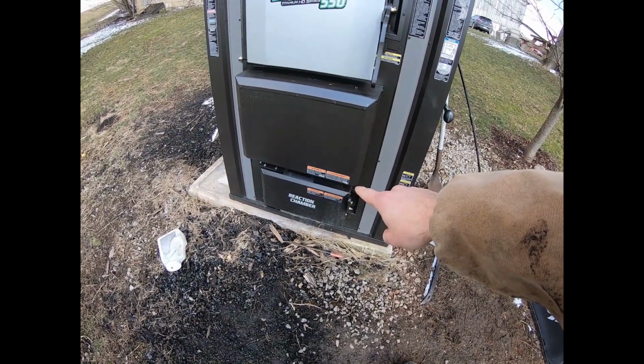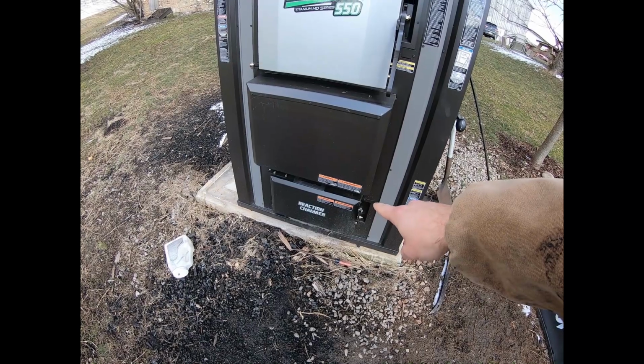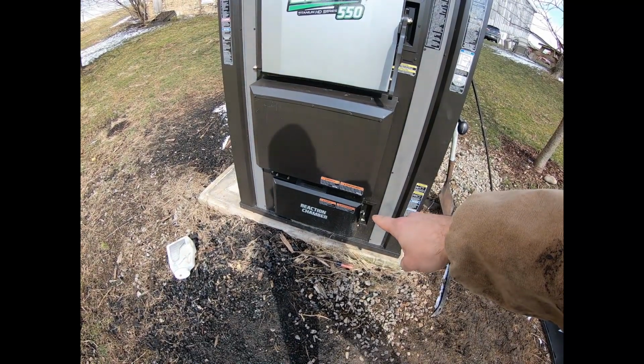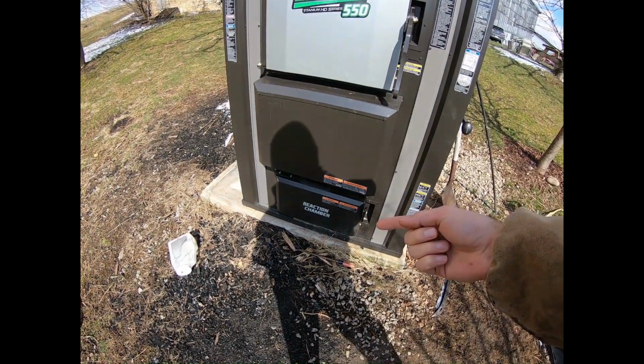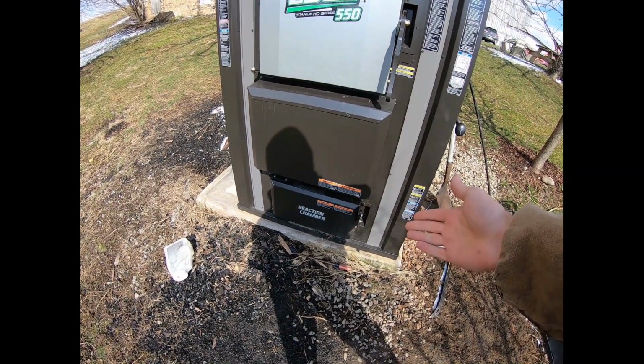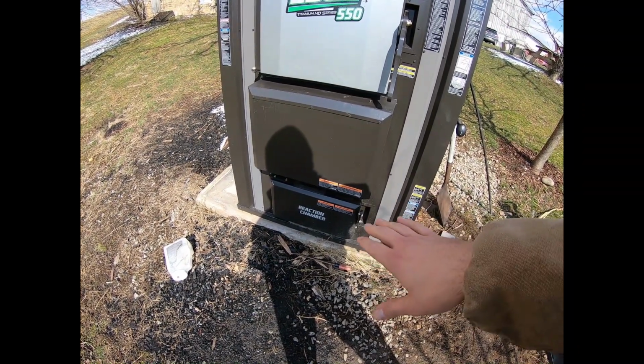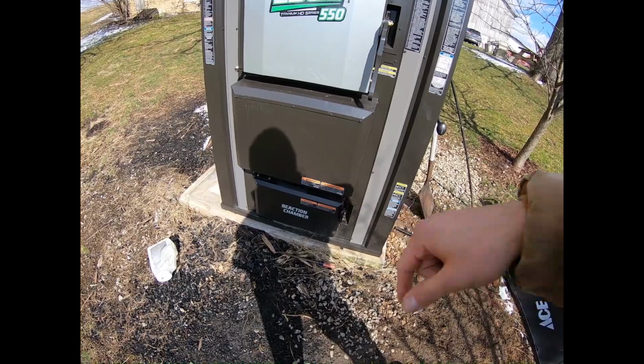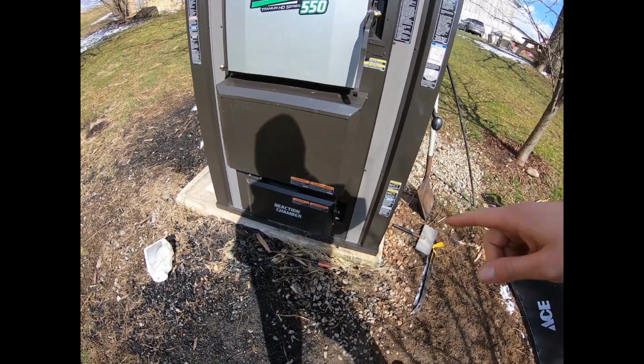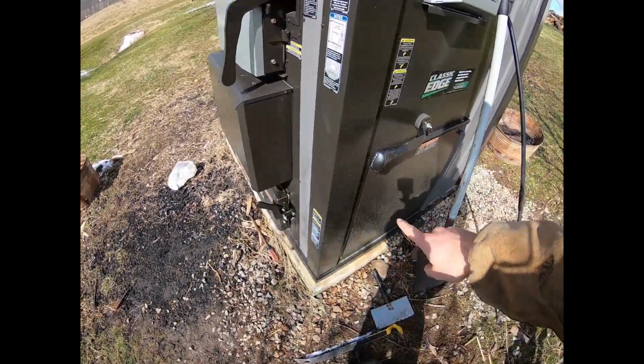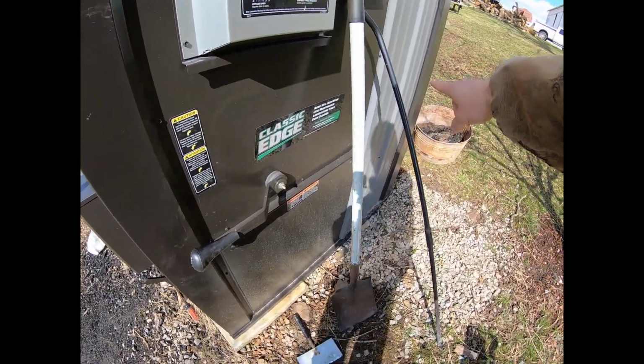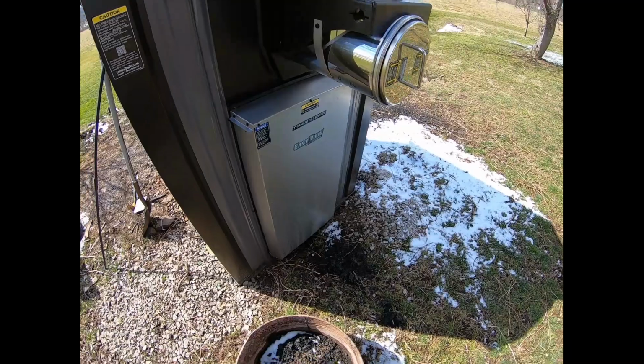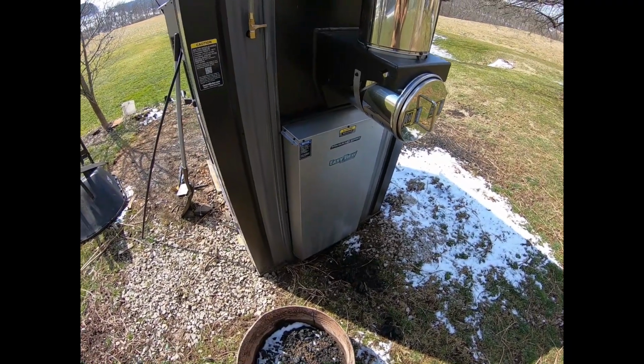In the reaction chamber, they actually add additional air to the gases that are coming down through, and it secondarily combusts. You normally can average somewhere between 1,000 to 1,400 degrees inside of this reaction chamber. As the gases travel through the furnace, it comes down through here, and they go up through the vertical heat exchanger, and that actually sits back here. That's where the Easy View heat exchanger is.